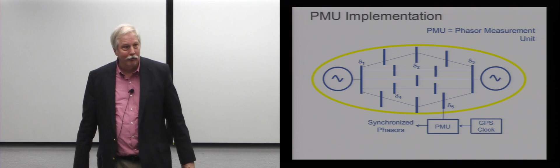Today, utilities are building synchrophasor systems in a hierarchy. The hierarchy says I have a measurement in a substation. The substation data gets collected by a device known as a phasor data concentrator, often abbreviated as a PDC. The phasor data concentrator sends it up to the local controller. The local controller then sends it up to what's called the independent system operator.